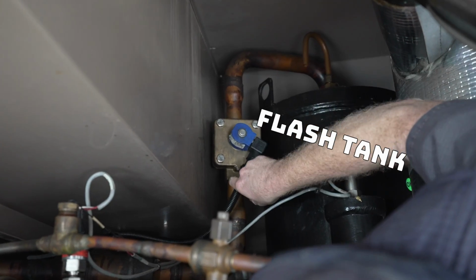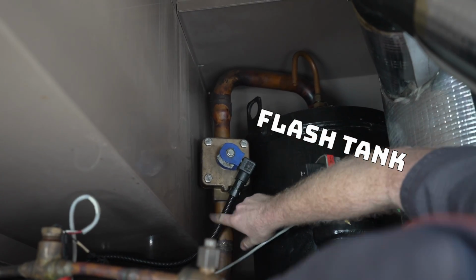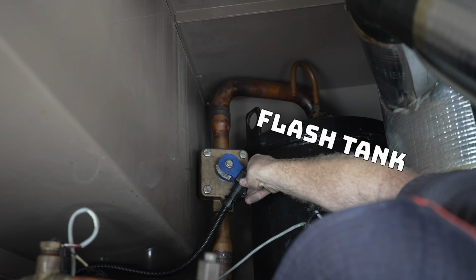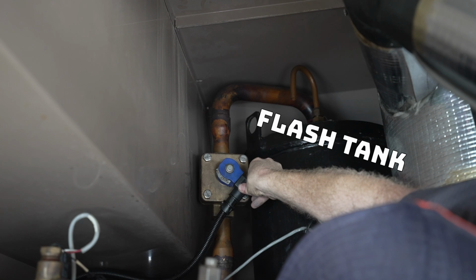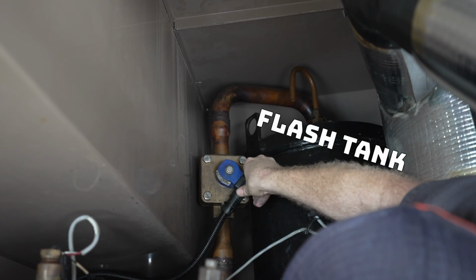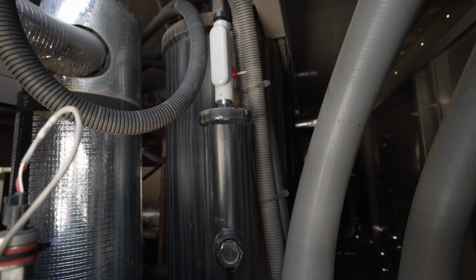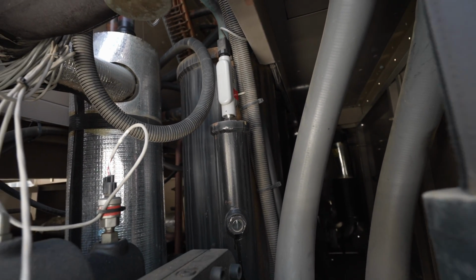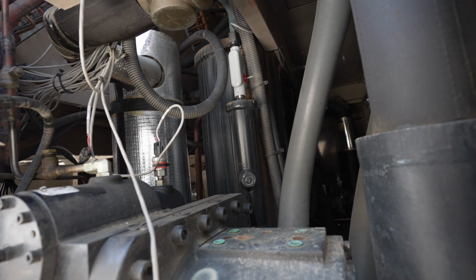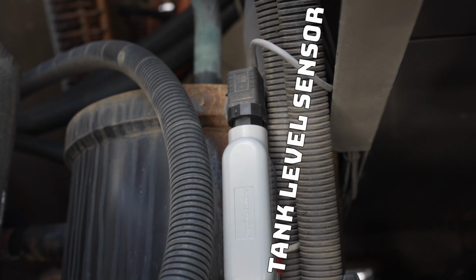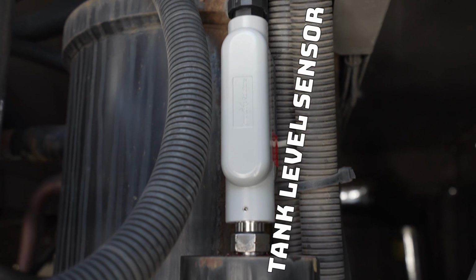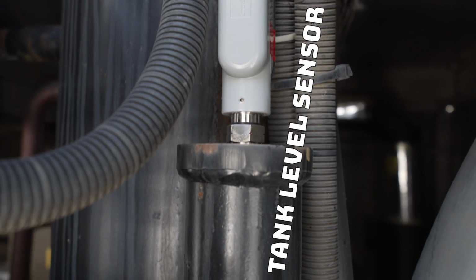Now, the second way we do this is through a flash tank assembly. So flash tanks are quite literally what they sound like. We're going to take the refrigerant, we're going to pre-flash it going into this holding tank. Now, this tank, what it allows to happen is the refrigerant that is flashed, which is now a gas, will rise to the top of the tank, and the liquid that stayed a liquid will be at the bottom. Now, this is what happens with any metering device. You go to a regular air conditioning coil and you have your TXV, you get your 80-20 or 75-25 split, however you want to term that, coming out of the metering device going into your coil.